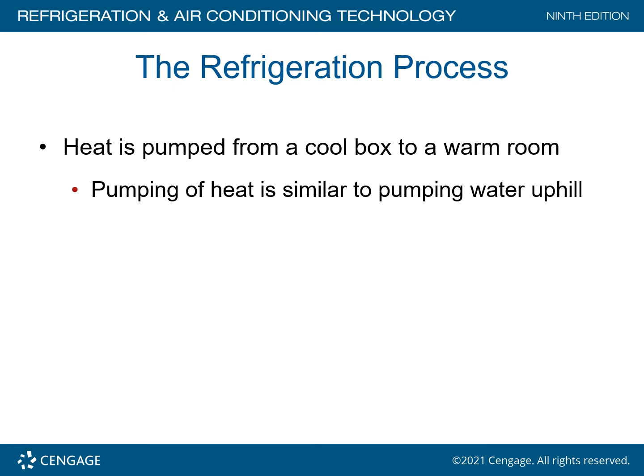Now, I want to go on record as saying all air conditioning compressors that you are going to be dealing with, all refrigeration compressors that you are going to be dealing with, are designed to pump vapor, low pressure vapor. No compressors are designed to pump liquid refrigerant. That doesn't mean a compressor can't pump certain amounts of liquid refrigerant when there is a low demand. Some compressors are designed heavy enough to withstand some liquid going into the compressor. But as a theory of operation, all compressors are designed to pump low pressure refrigerant vapor. And we'll talk more about that in a bit.